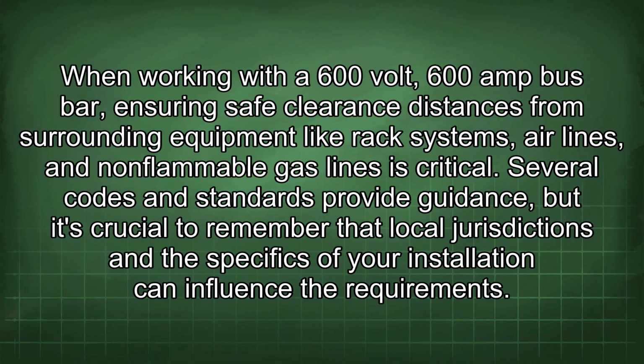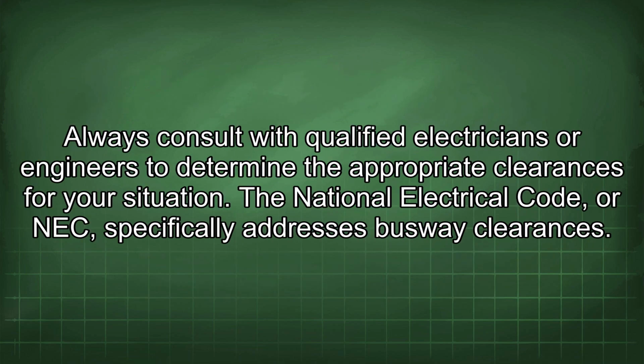When working with a 600-volt, 600-amp bus bar, ensuring safe clearance distances from surrounding equipment like rack systems, air lines, and non-flammable gas lines is critical. Several codes and standards provide guidance, but it's crucial to remember that local jurisdictions and the specifics of your installation can influence the requirements. Always consult with qualified electricians or engineers to determine the appropriate clearances for your situation.